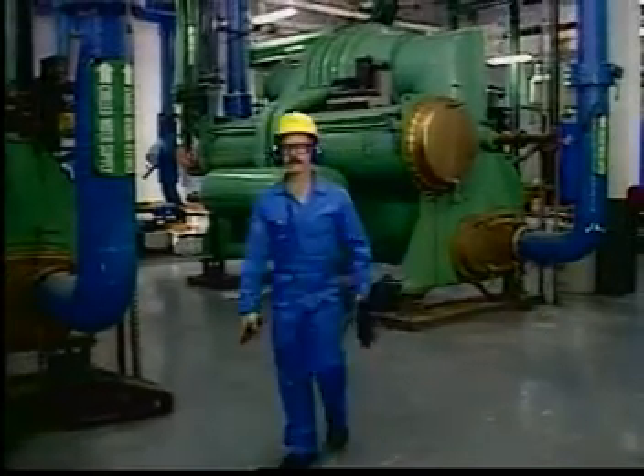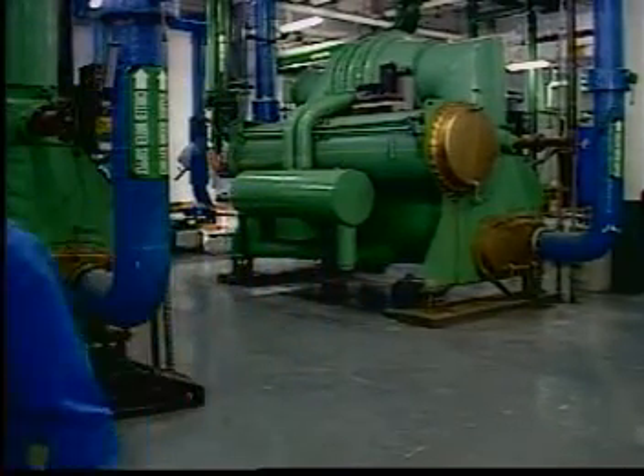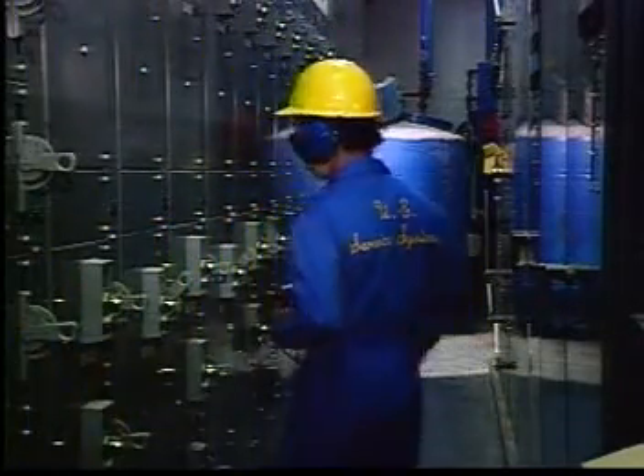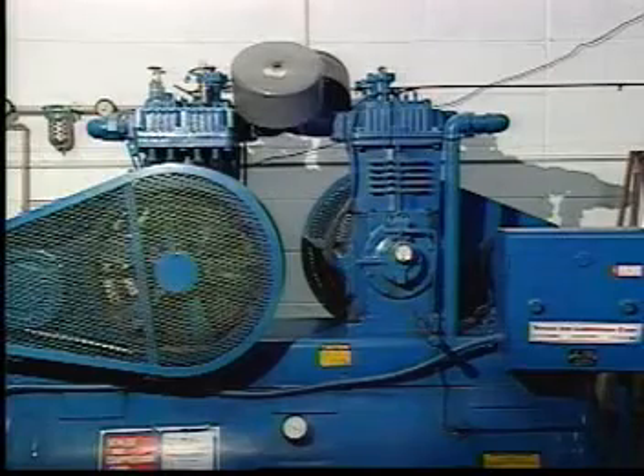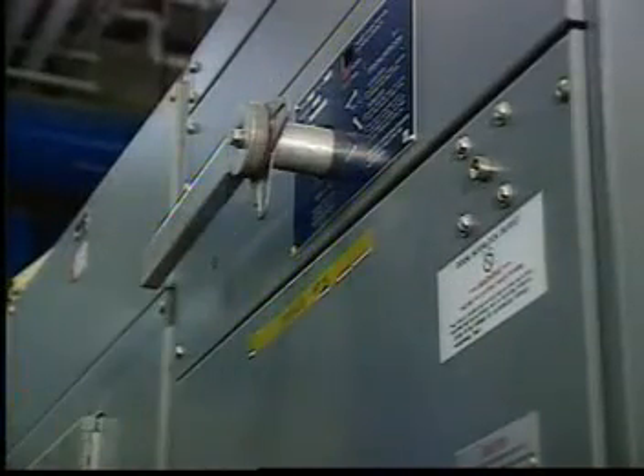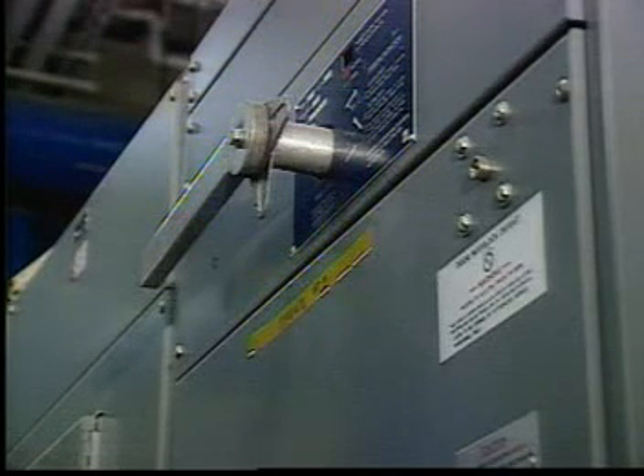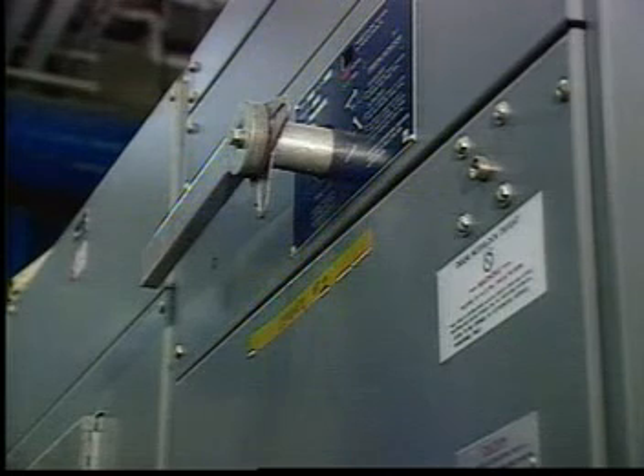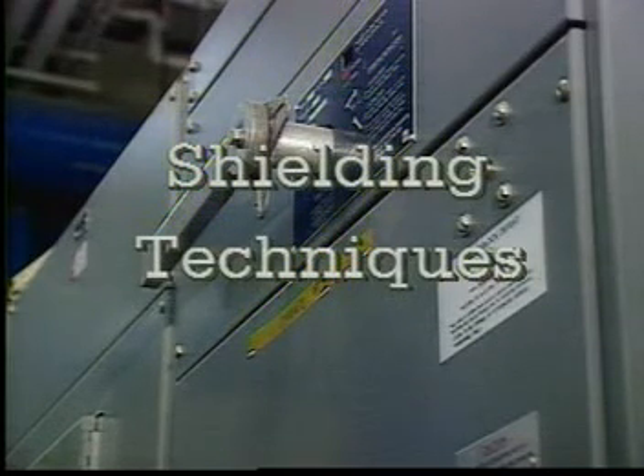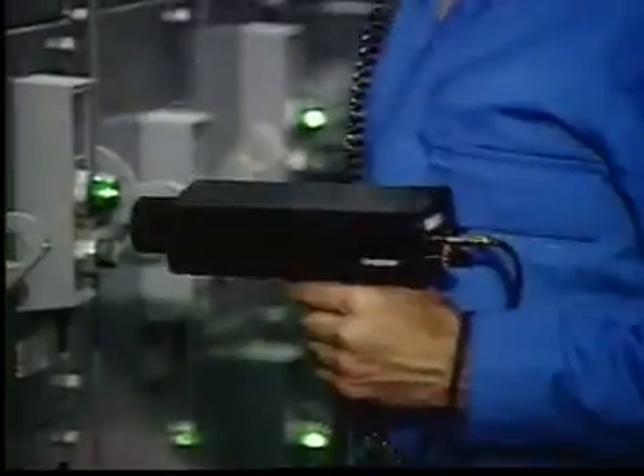Another testing situation which may require advanced techniques is a noisy environment. In certain plants, when working with mid and low voltage equipment, for example, you may need to avoid potentially confusing stray sounds. This may be as simple as shutting a door. When possible, it is best to turn off the source of competing ultrasound. However, it may be difficult or impractical to turn off competing sounds. In these situations, various shielding techniques can be used effectively to block out competing signals.